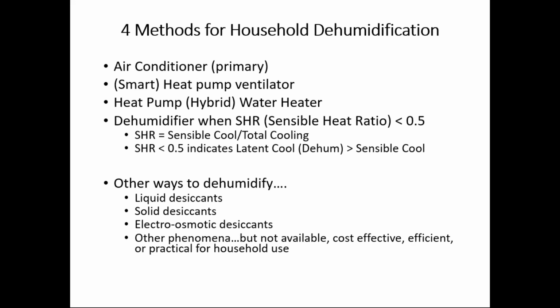and putting that into your hot water. And then finally, the dehumidifier, based on the sensible heat ratio. The sensible heat ratio is the sensible cooling, the cooling that goes to changing the temperature of air, where we describe latent cooling as the energy that goes to changing the humidity. It's kind of hidden. It's changing moisture level, but not necessarily temperature level. If we take the ratio of the sensible cooling to the total cooling, if that ratio gets less than 0.5, or more than 50% of the cooling is for latent, then typically a dehumidifier would be desirable. And above 0.5, the other three should be, in many cases, able to handle the moisture load.